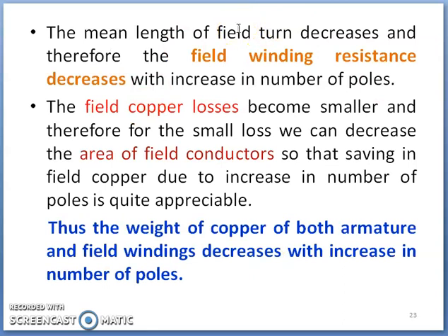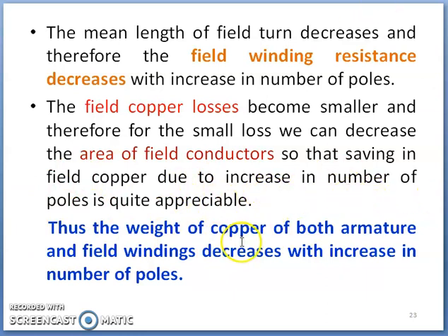What happens to field winding resistance and field copper loss? As the mean length of the field turn decreases due to a large number of poles, the field winding resistance decreases with increase in number of poles. At the same time, field copper loss becomes smaller. If losses are small, definitely the area of field conductors required will be less because field copper loss will be less due to increase in number of poles. Thus, the weight of copper of both armature and field winding decreases with increase in number of poles — the requirement of copper will be less for both armature and field sections.